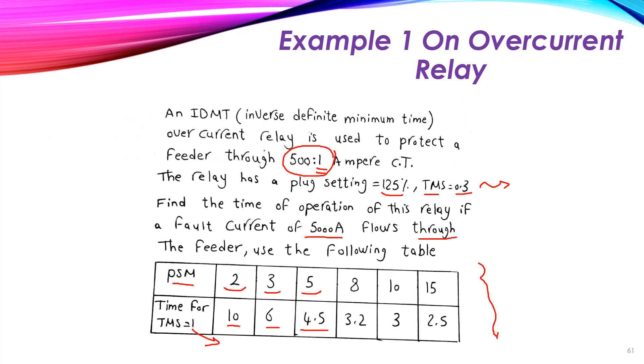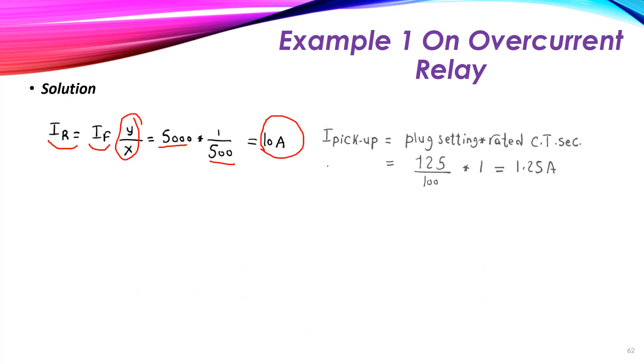Now, to use the table we need the plug setting multiplier (PSM). For that, we need the pickup current. The relay has a plug setting of 1.25, which is 125% of the CT secondary rated value of 1 ampere. So the pickup current equals the plug setting multiplied by the rated CT secondary current: 1.25 × 1 = 1.25 amperes.